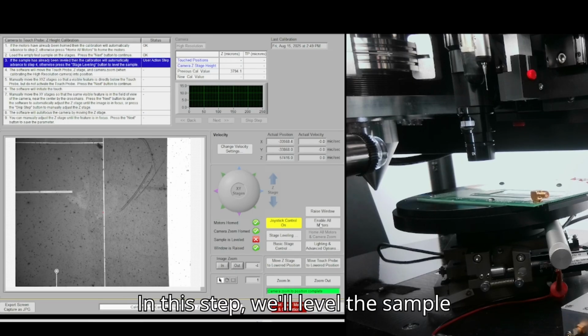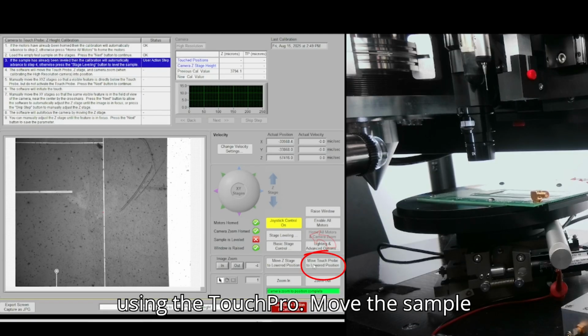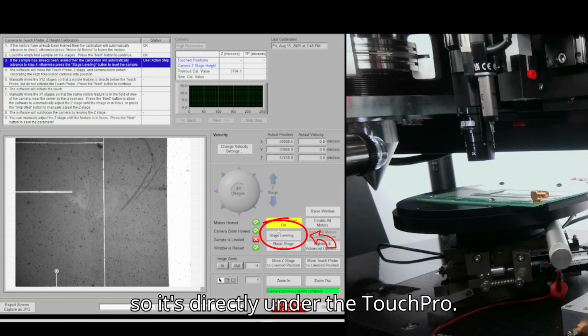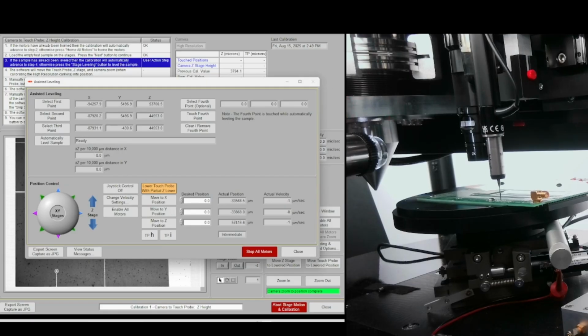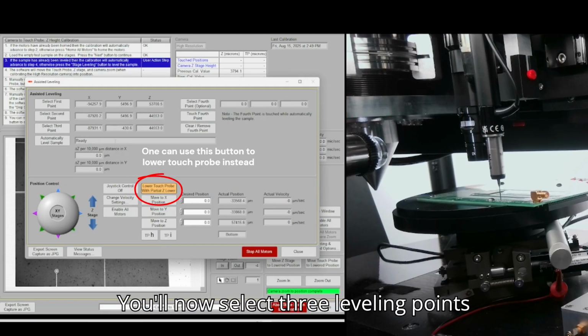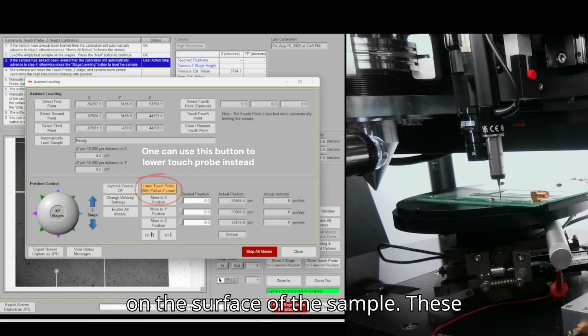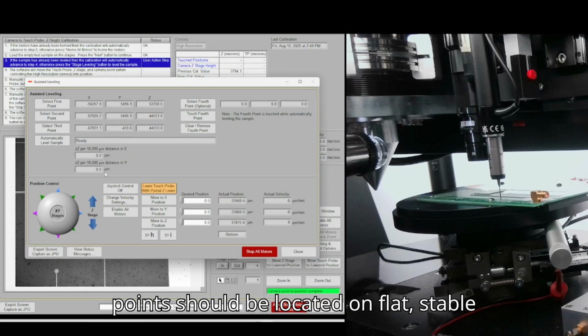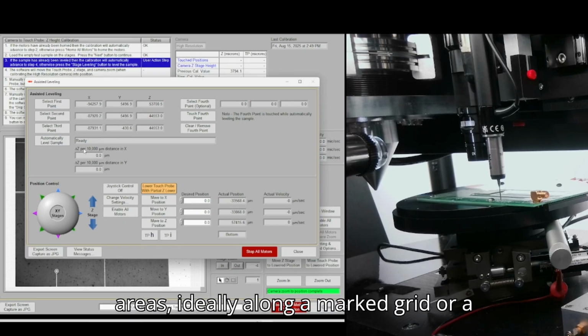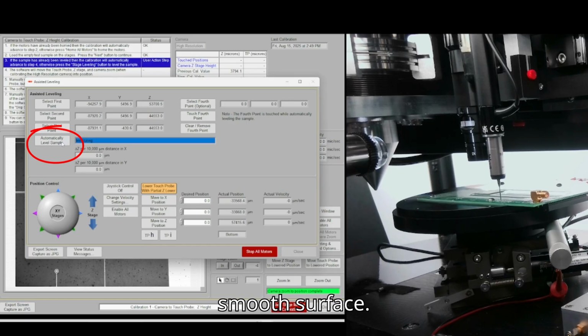In this step, we'll level the sample using the Touch Probe. Move the sample so it's directly under the Touch Probe. You'll now select 3 leveling points on the surface of the sample. These points should be located on flat, stable areas, ideally along a marked grid or a smooth surface.